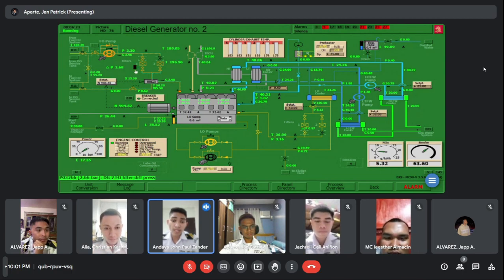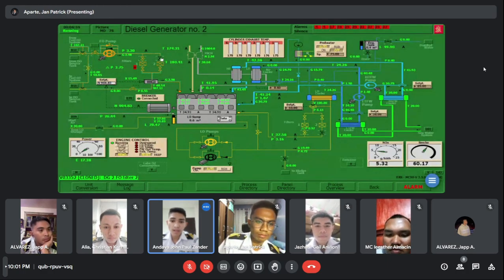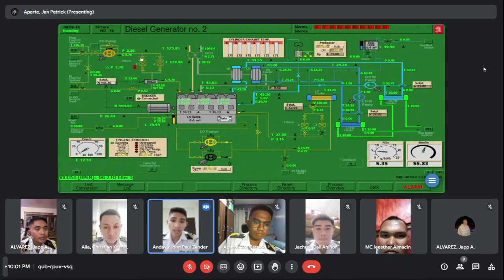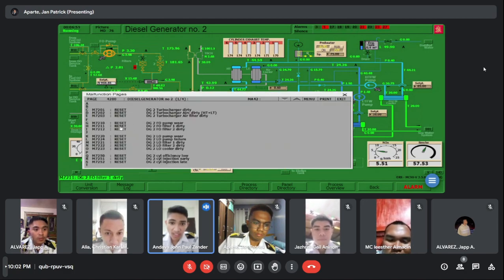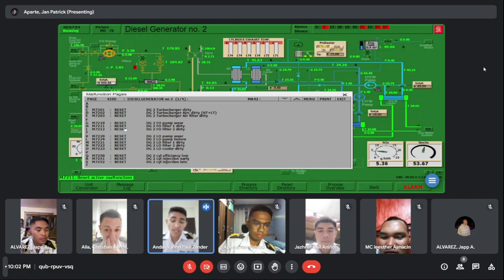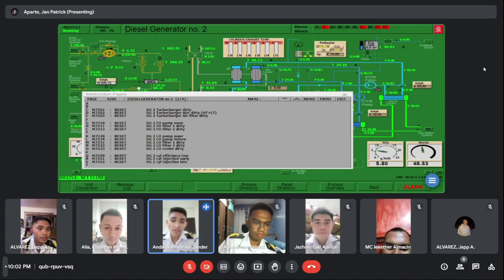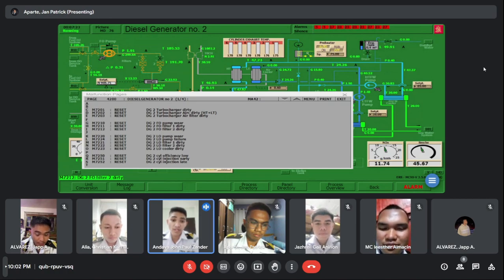You see that fuel filter 1 alarmed. So acknowledge the alarm. After acknowledging the alarm, open the bypass valve or the pressure fuel filter number 2 so they can be interchanged. Then for fuel filter number 1, go to letter M and find letter H, which is diesel generator number 2, fuel oil filter number 1 is dirty. That is why it alarmed, so we just reset it. Then reset the active malfunction. Turn filter 1 back on, then turn off filter number 2. After turning off filter number 2, we reset just to make sure we rectified both filters. So okay.